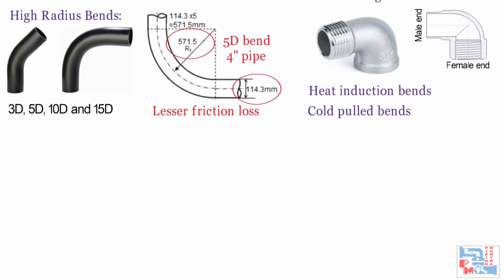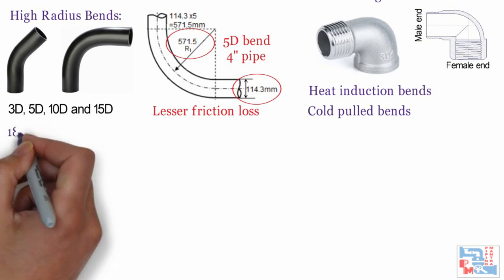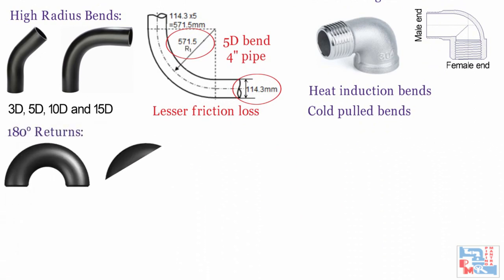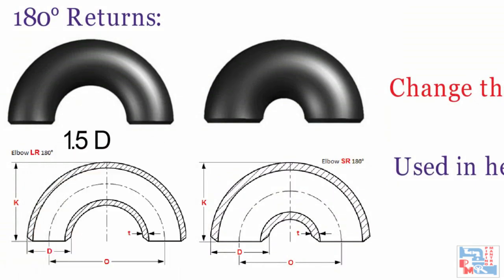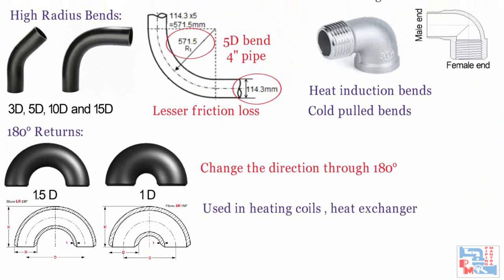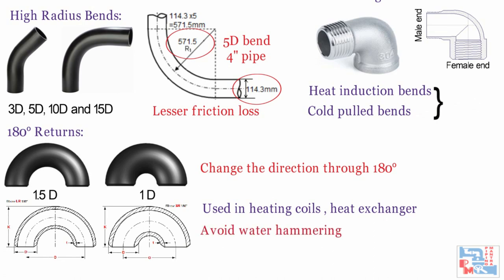Let's discuss other pipe fittings. The 180-degree return changes the direction through 180 degrees and is mainly used in heating coils and heat exchangers. These are available in 1.5D and 1D bend radius. This fitting greatly reduces water hammering effect and is used where pressure drop is critical.